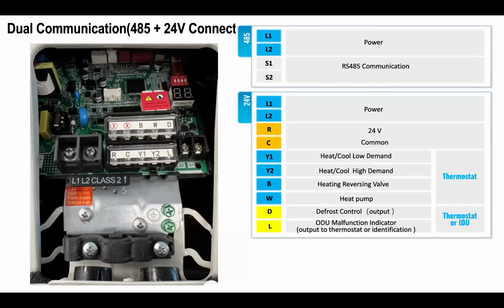D and W are going to confuse people. Now, this is only applicable if they use a 24 volt thermostat or 24 volt full control. W is actually an input from the indoor unit, from the 24 volt thermostat, that puts the heat pump in heating mode.